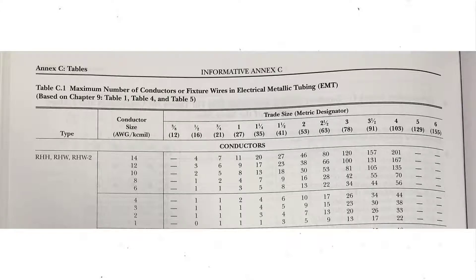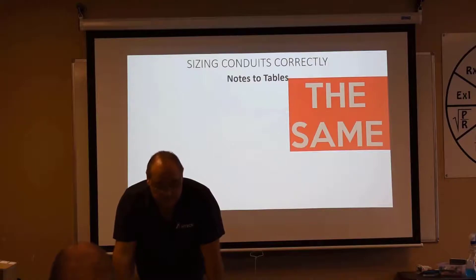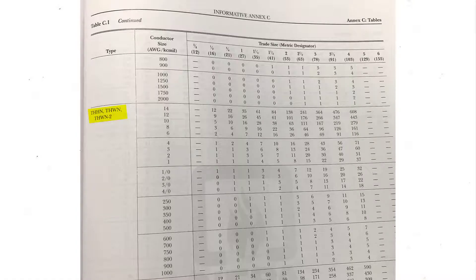Annex C in the 2020 code starts at page 730. That's Table C1, which gives the maximum number of conductors or fixture wires in EMT — electrical metallic tubing. Write 'EMT' at the top of pages 730 and 731. Find THHN, THWN, THWN-2 and highlight that. You'll see wire sizes from 14 down to 1,000. Scrolling left to right shows different trade sizes of conduit. For a typical 3/4-inch EMT, look up how many #10 or #12 THHNs fit. This table is based on 40% fill and does not go beyond that. For 2-inch EMT, you can fit 4 four-aught conductors.